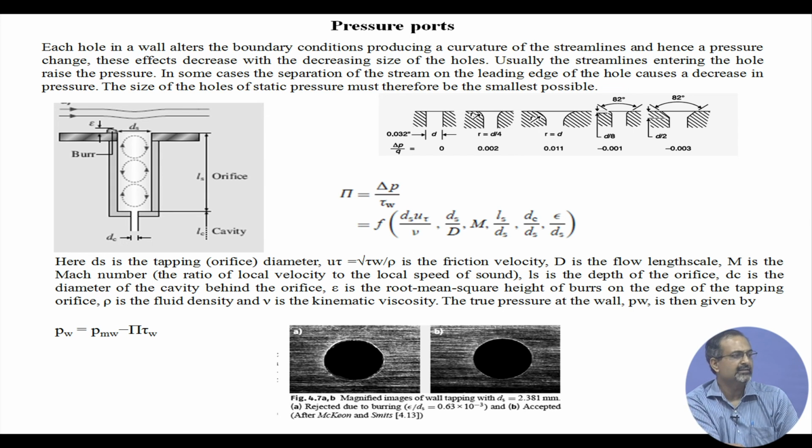In that case, the diaphragm region has to be closest to where you would like to make the pressure measurement, where you need to pick up the signal from. If you take it far away from the source, you are going to lose information. So here we are not talking about such measurement. This is an orifice based design.